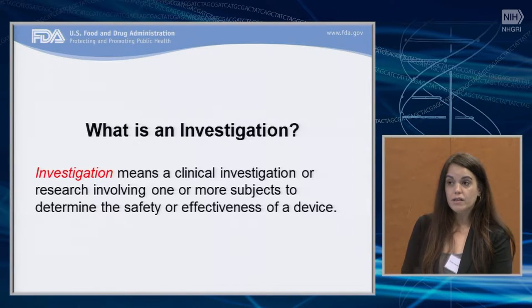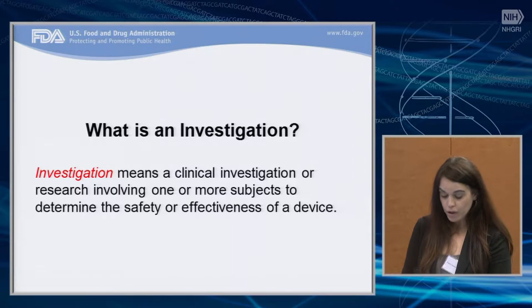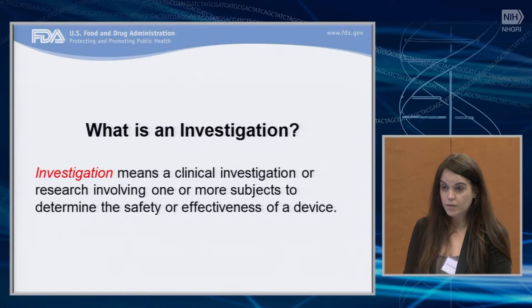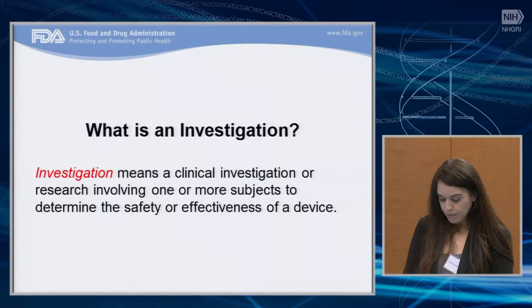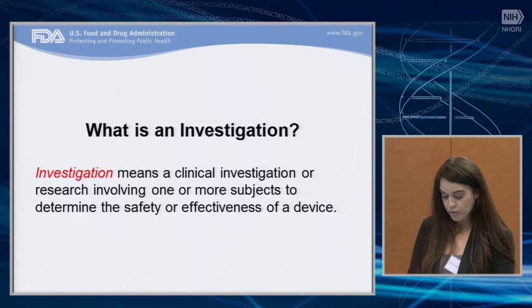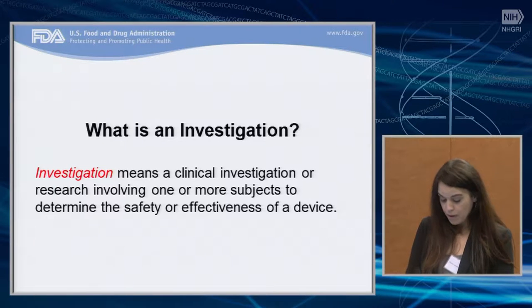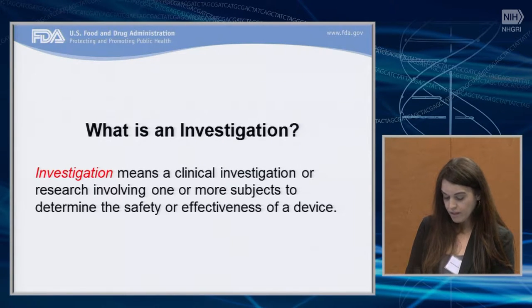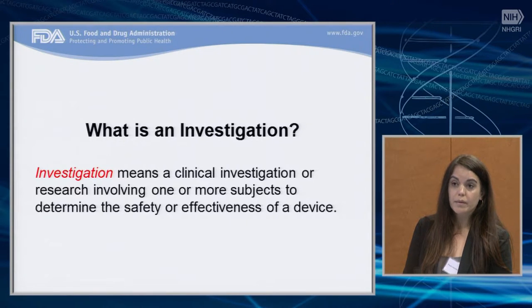The term investigation does have different meanings in different parts of our regulations. This is from the investigational device exemption regulations. An investigation is defined as a clinical investigation or research involving one or more subjects to determine the safety or effectiveness of a device. It's important to note that even if determining the safety and effectiveness of a device is not the specific goal of an investigation, if you're learning about the device or learning about its safety or effectiveness, then you are performing an investigation.